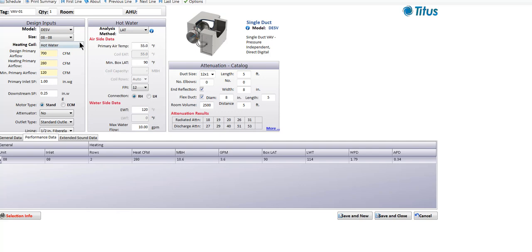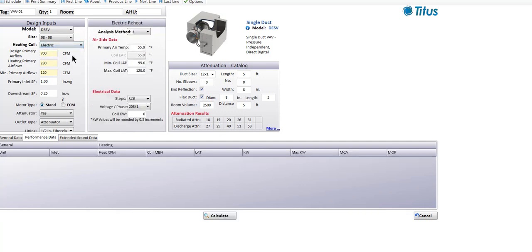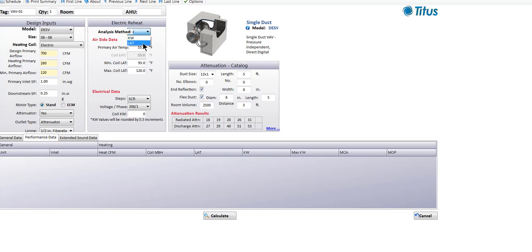Now let's look at a different type of box — a selection with an electric coil on a fan-powered box. When selecting an electric coil, we would typically go with the same kind of air flow rates as if we had a hot water coil. We have fewer selection methods here: we can select based on kilowatts or leaving air temperature, defaulting to 95 degrees — I like to knock that down to 90 degrees.